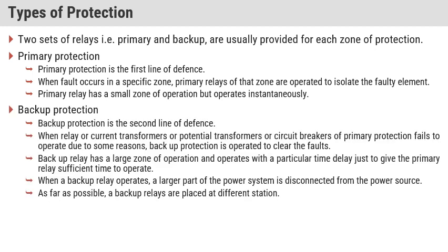And what is backup protection? Backup protection is a second line of defense when a relay, a current transformer, a potential transformer, or a circuit breaker of the primary protection fails to operate for some reason. Backup protection operates to clear the faults.